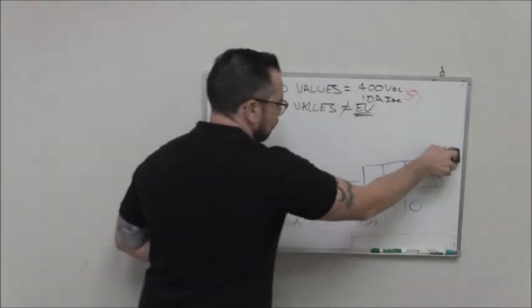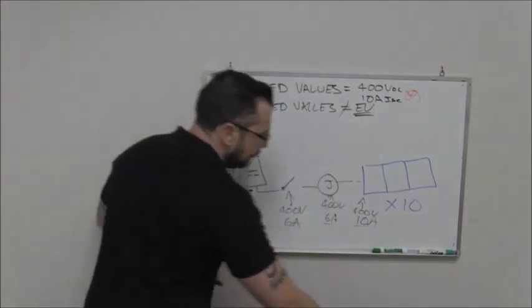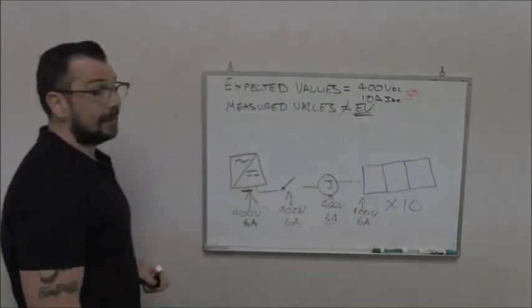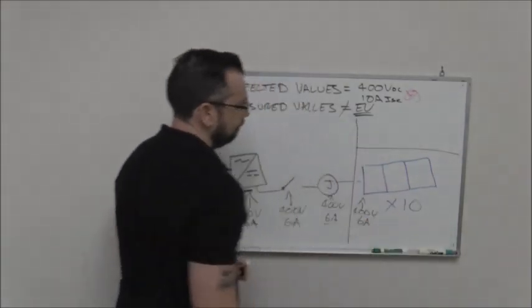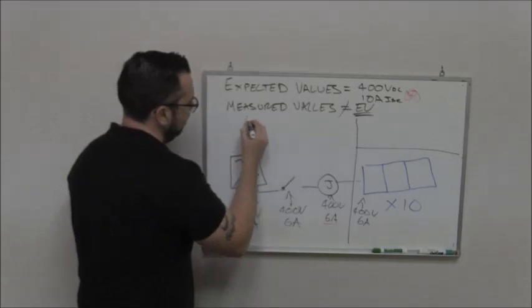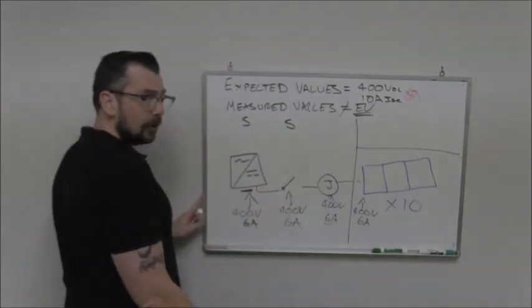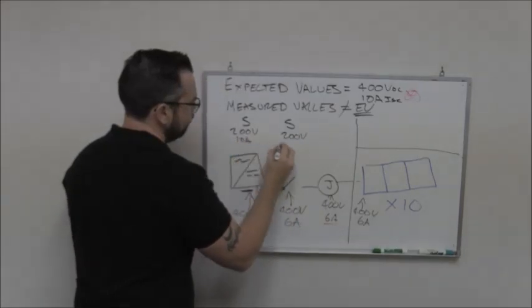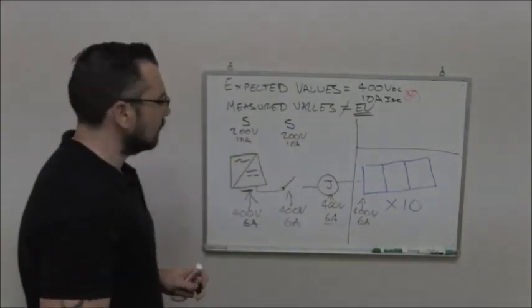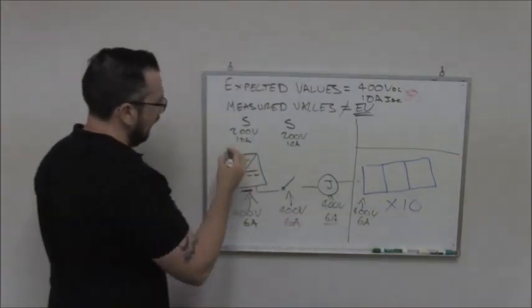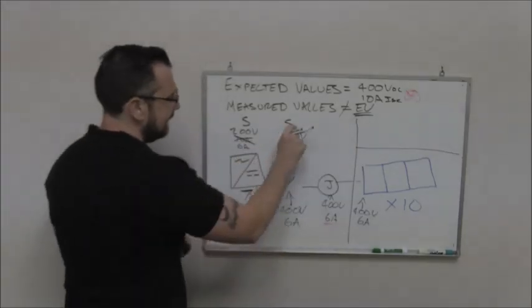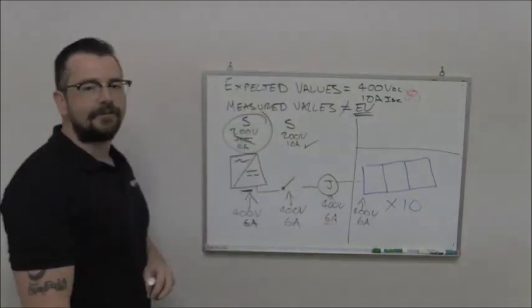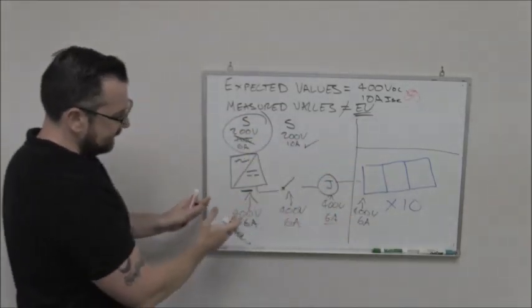So similarly, if my measured values here was still not what I expected, now I know the problem is in this section. So what do I do? I have 10 panels. I split them into 5 and 5. The voltage is going to drop by half. The current is going to stay the same. So I test this 5 with my PV150, and this comes out at 6 amps. I test this half, and it comes out as 10 amps. Now I know the problem is in this half.